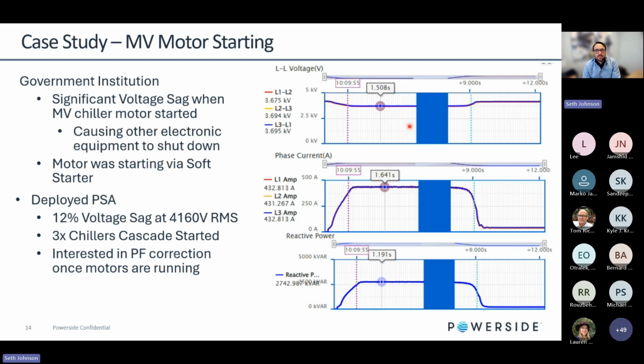One of the things we can do with medium voltage motor starting is provide voltage support by adding reactive power to the system. Whether the motor is on a soft start or direct across the line, there's a significant amount of reactive power being consumed during that motor starting process. So you can see here, this is the reactive power needed to support the motor starting sequence on the soft start, which was just under 3 megavar, or 3000 kvar. And if you were able to correct all of that, that would give you a unity power factor. But of course, we're looking at providing capacitors. So, okay, we want to take care of the voltage issue during the motor starting, but also we want to correct for power factor. While we're in there adding vars to the system, let's try to tackle both problems at the same time.